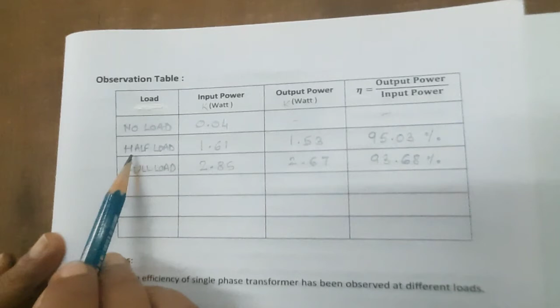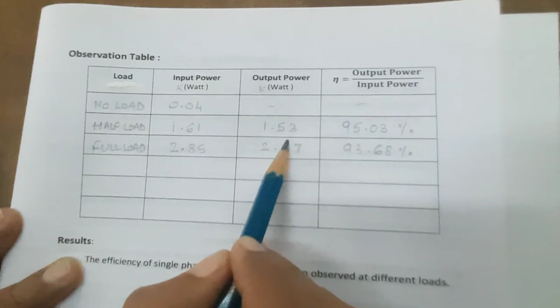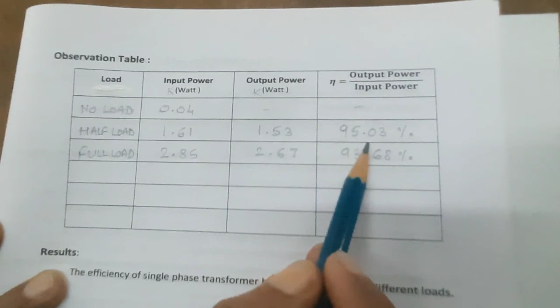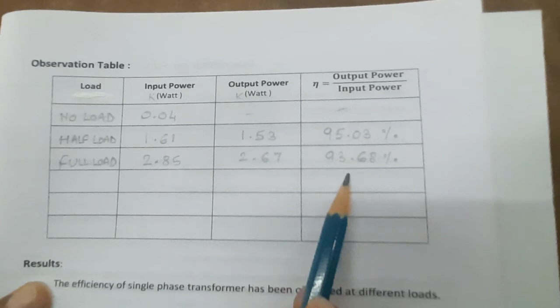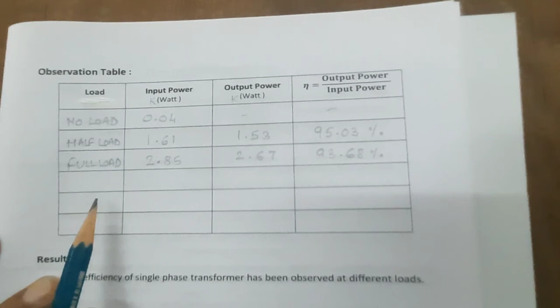For the half load, this is the reading for the primary input power and the secondary output power. We take the ratio of output by input power, which gives the efficiency in percentage. Similarly for full load, we take the input power and output power and calculate the efficiency by taking the ratio. In this manner we have to make the observation table.